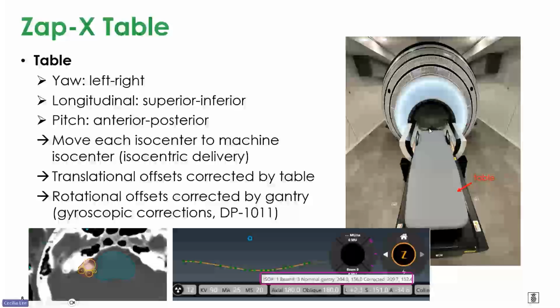The table has a unique motion. It's a 3 degrees of freedom couch, but when the table goes in and we want to move the patient left and right, it actually uses yaw instead of translation. And then longitudinally, the table can go in and out, moving the patient in the superior and inferior direction. And then using pitch angle, we move the patient in the anterior-posterior direction. So what the table does is move each isocenter to the machine isocenter.